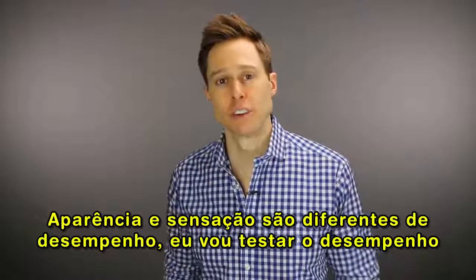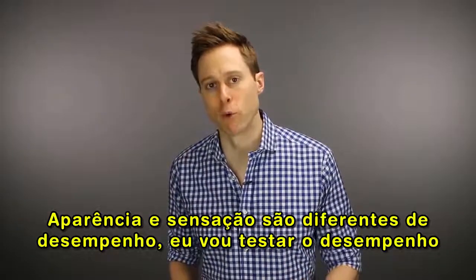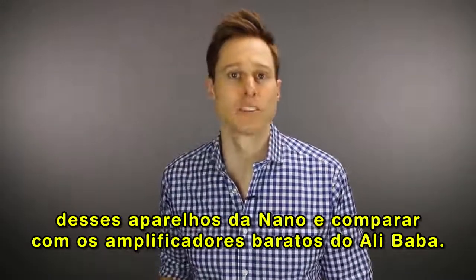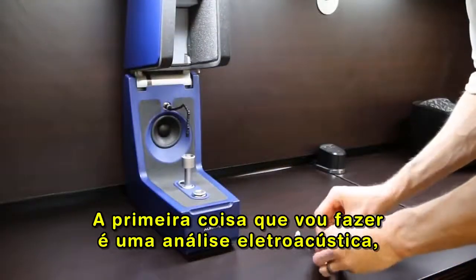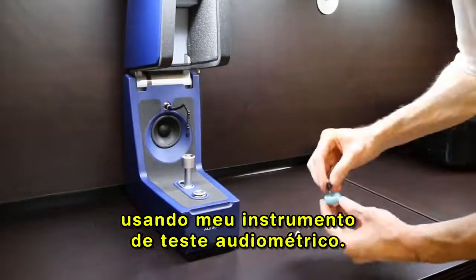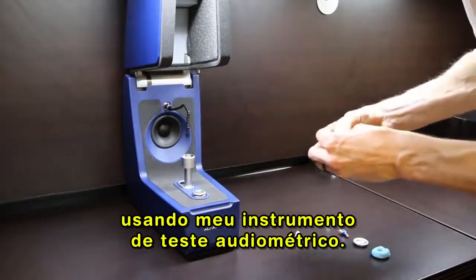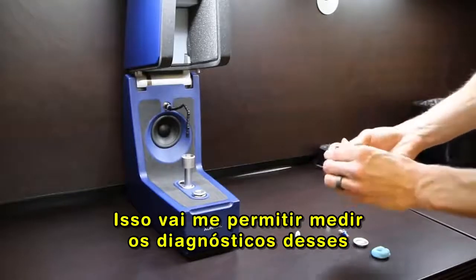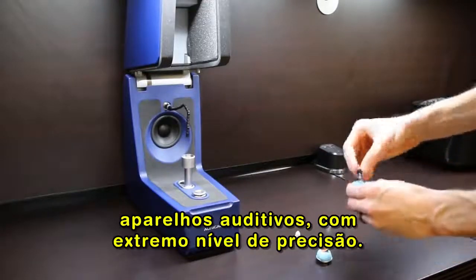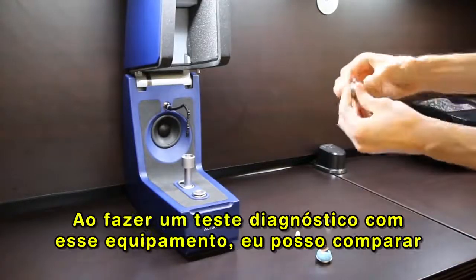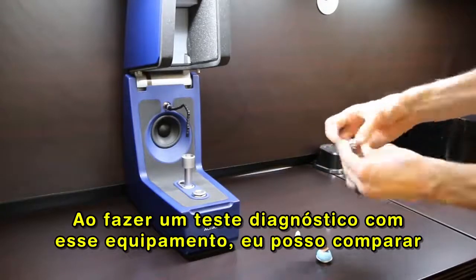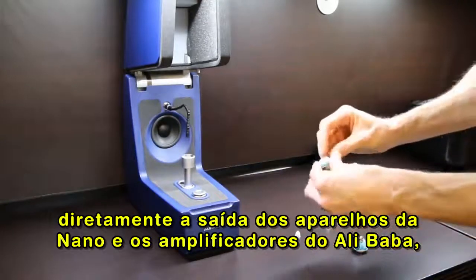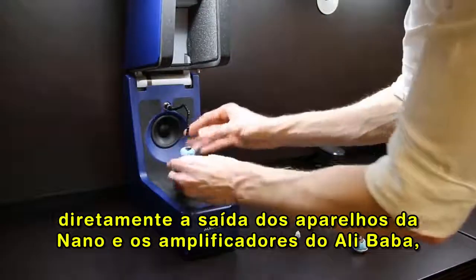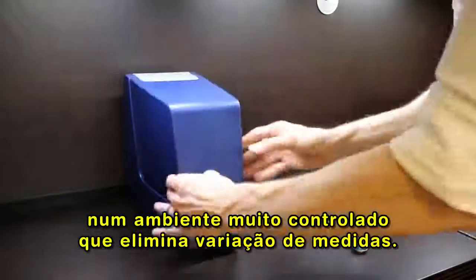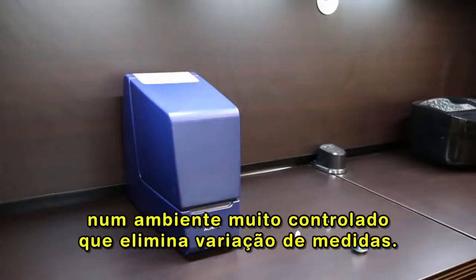Now, look and feel are different than performance, so I'm going to test the performance of these NANO hearing aids up against these cheap Alibaba amplifiers. The first thing that I'm going to do is electroacoustic analysis using my Audiometrics hearing instrument test box. This will allow me to measure the diagnostics of these hearing aids with an extremely high level of accuracy. By doing a diagnostic test with this equipment, I can directly compare the output of the NANO hearing aids with the Alibaba amplifiers in a very controlled environment that eliminates variability of measurement.